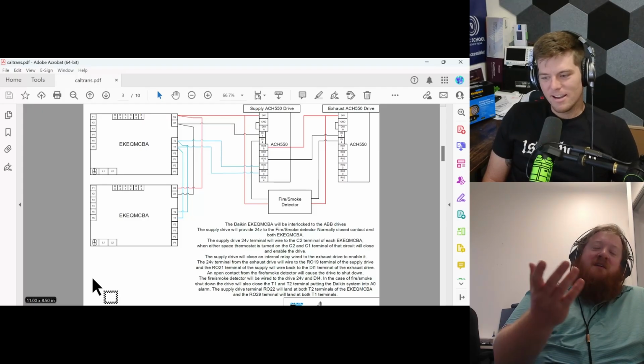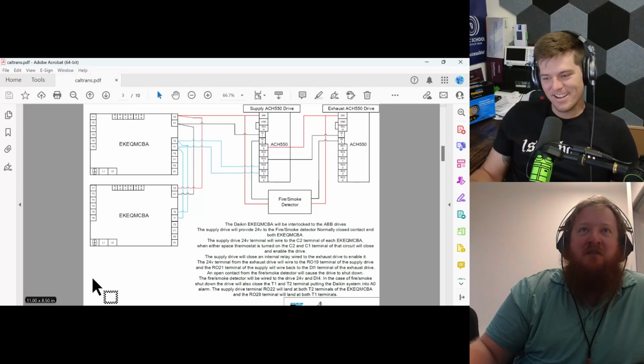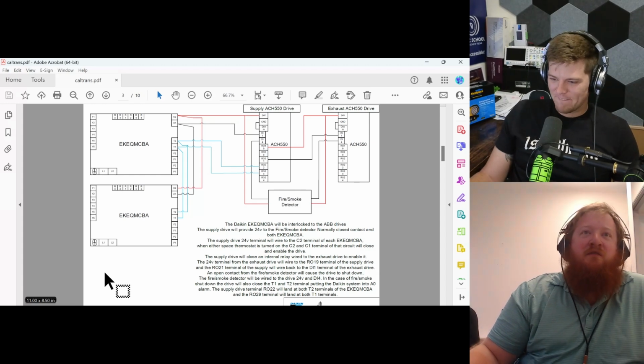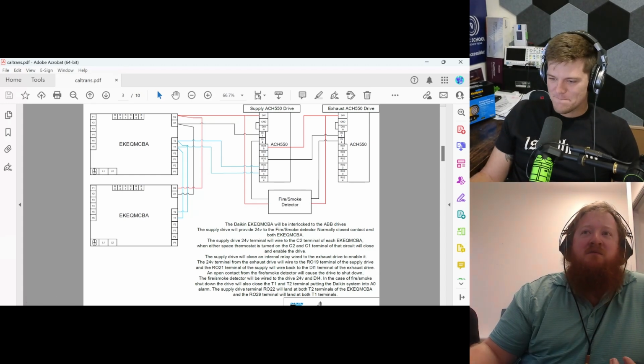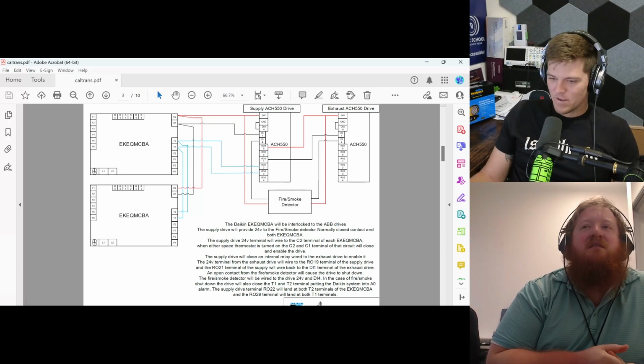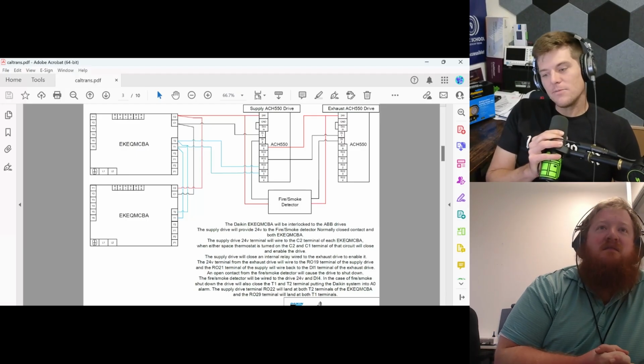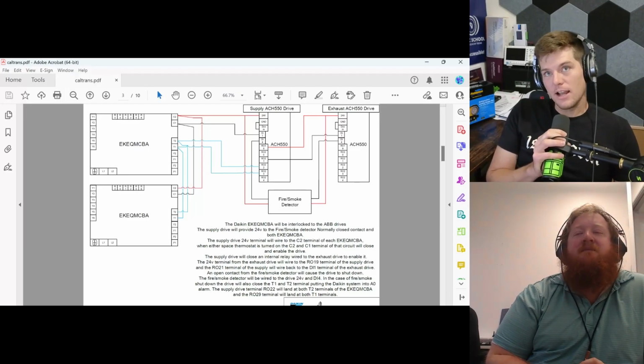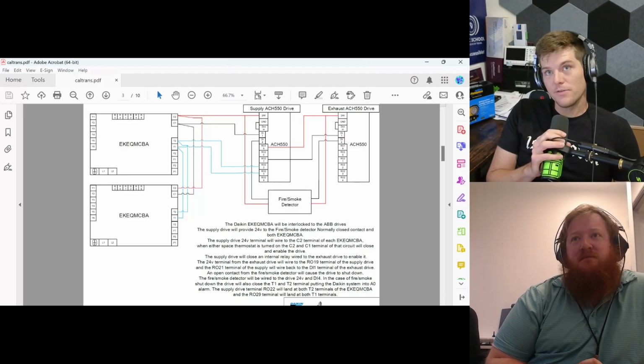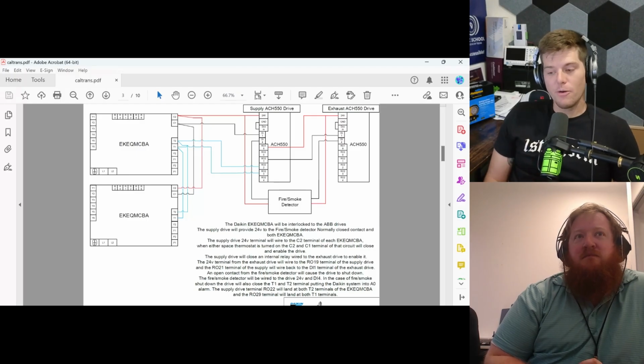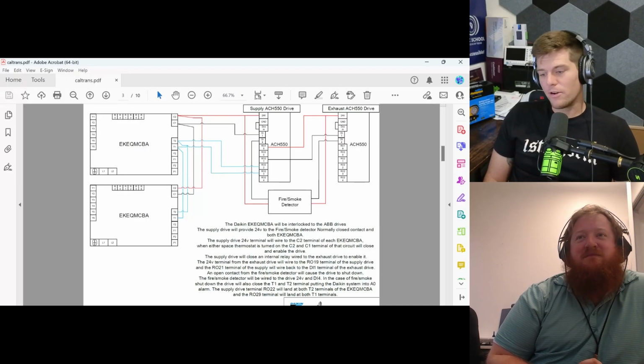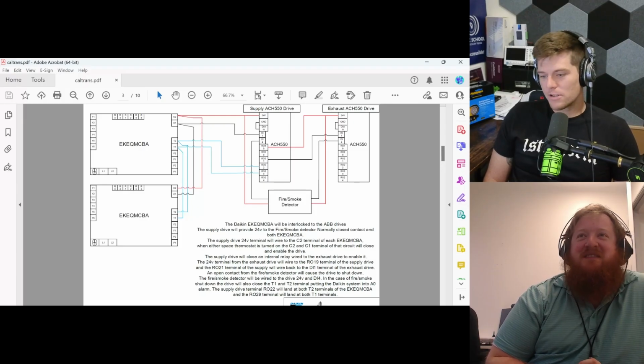That brings up a good topic - should any fire life safety call be automatically reset? I don't think it should be. Well, when we're talking about it, I see a lot of guys who change out VFD drives for Danfoss compressors and don't go back and set the auto reset. So anytime there's a manual trip, whether it's low superheat or a power cycle...